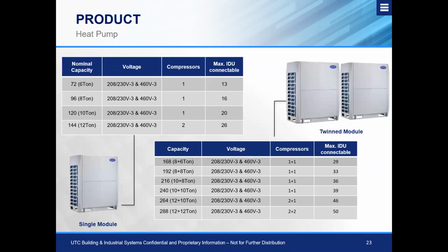Now with the heat pump style systems, you'll see here with our 6, 8, and 10 ton, we still offer that one compressor per outdoor unit on the single module. Now with the 12 ton is where we start stepping up with the dual compressors in there. And of course, just like on the heat recovery, as we increase in tonnage, our maximum number of indoor units that we can connect to that one centralized outdoor unit does increase as well. But the nice part with that 12 ton, as we increase the amount of compressors, we increase our low ambient heating performance as well.